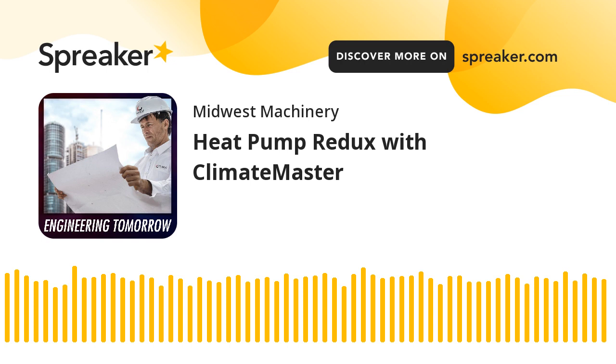The other component is we need to have a heat source in our loop. A heat source is used to maintain system water temperatures above 60 degrees. Typical heat source for a closed loop water source heat pump is a hot water boiler, and this could be either gas or electric. The fifth component is we need to have some way to reject the heat.